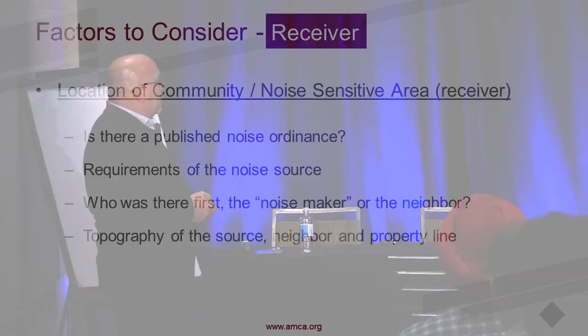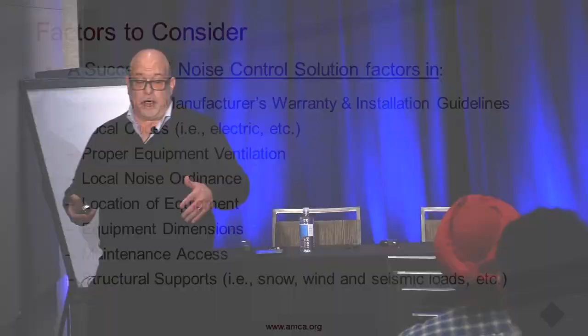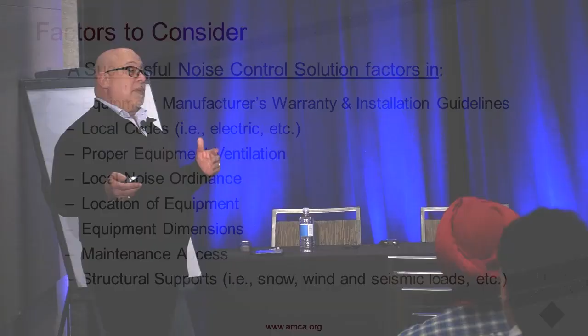We look at the equipment manufacturer's warranty and installation guidelines. If you need to put a barrier wall around, say, an air-cooled chiller, whether on a roof or at grade, you might make that wall out of acoustic louvers instead of acoustic panels, because the architect loves that look, and you get a lot of airflow at a low pressure drop. If we can stay within the guidelines—where the manufacturer says you shall stay this far away from these sides of the air-cooled chiller—that's beautiful.